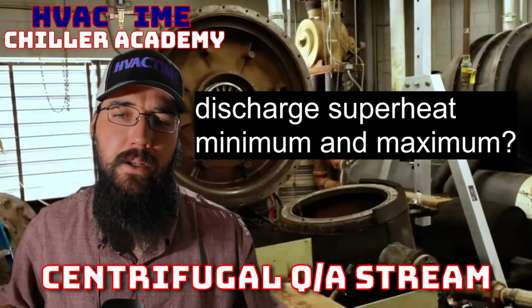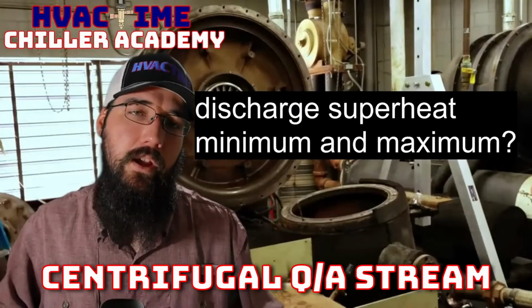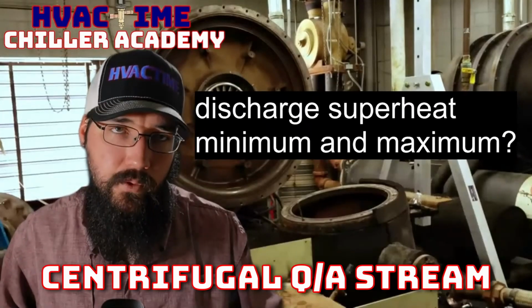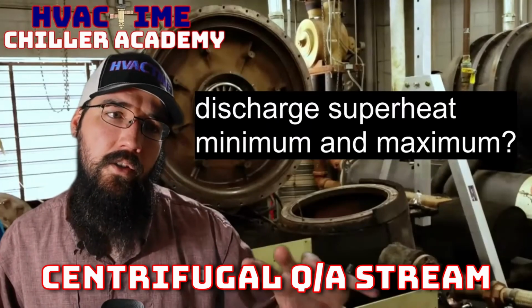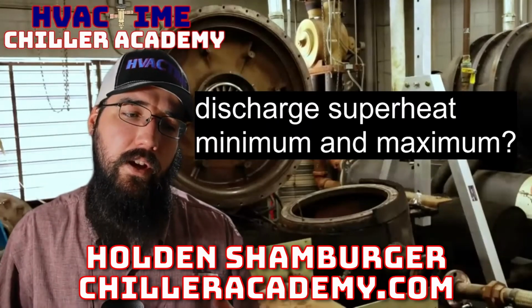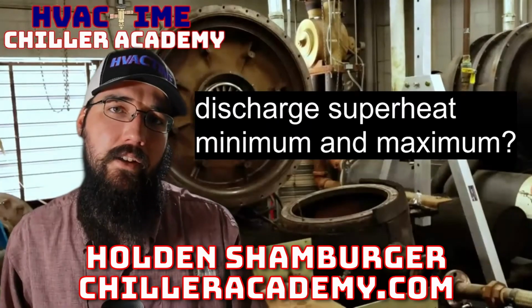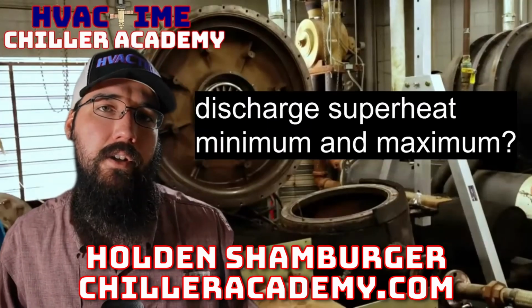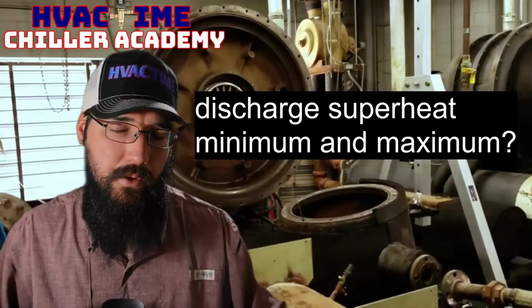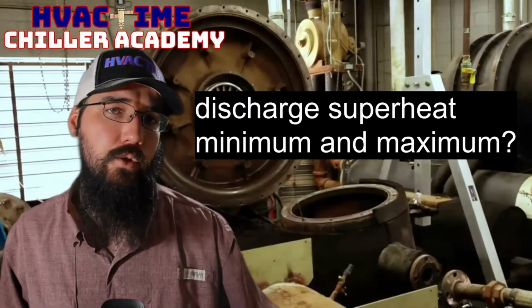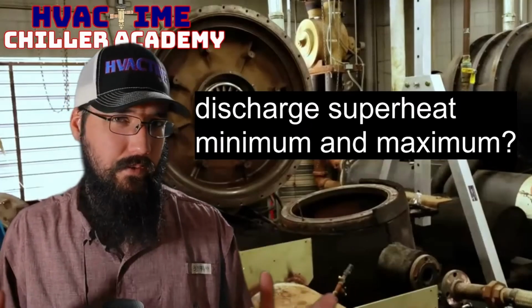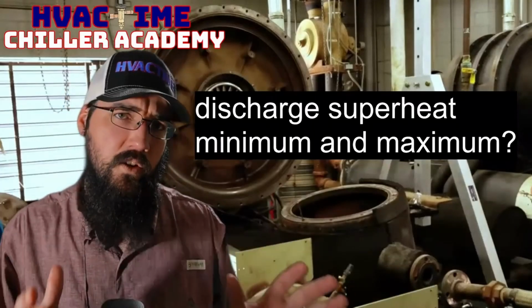All right, discharge superheat, minimum and maximum. In terms of a centrifugal, most of the time on the low end, if you've got a low load, or you're running a higher refrigerant level in your evaporator, which is going to drop your discharge superheat a bit, you'll typically see 10 to 15 degrees on the low end, right?